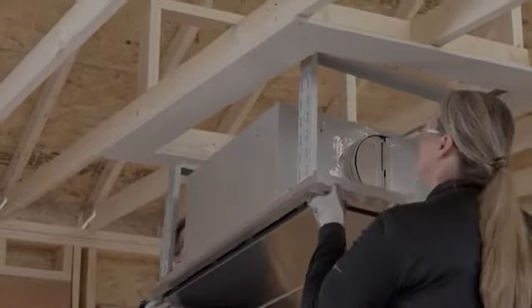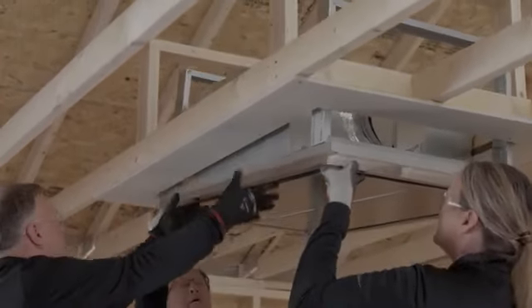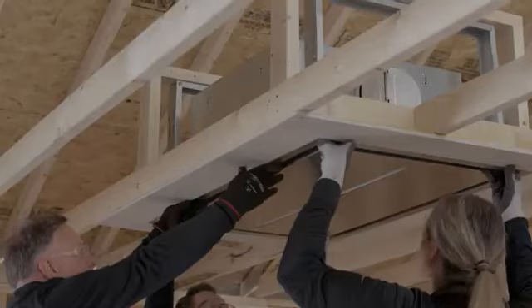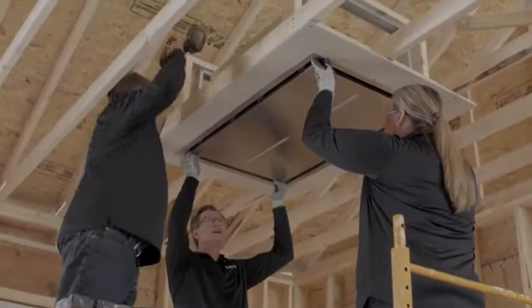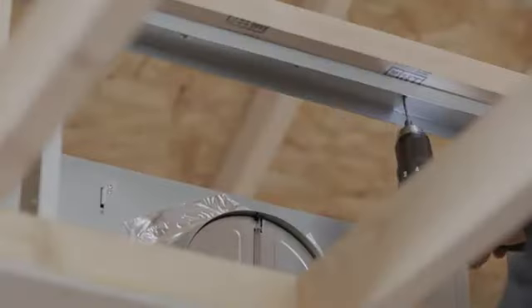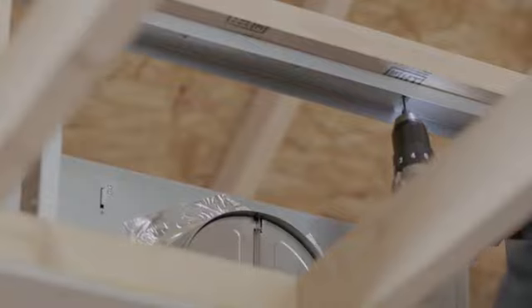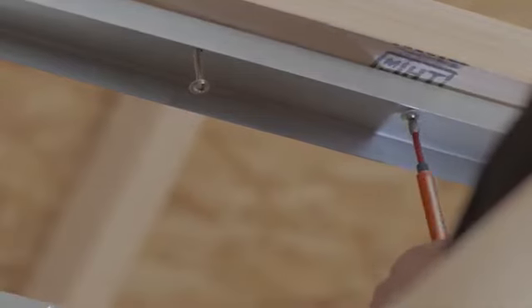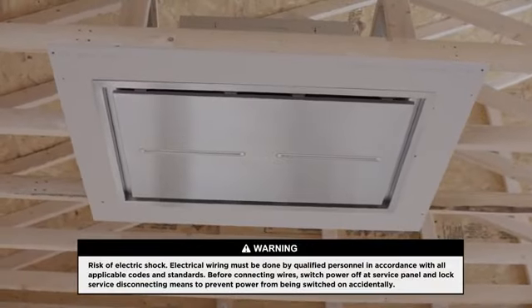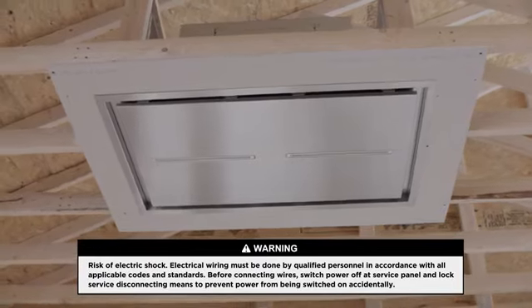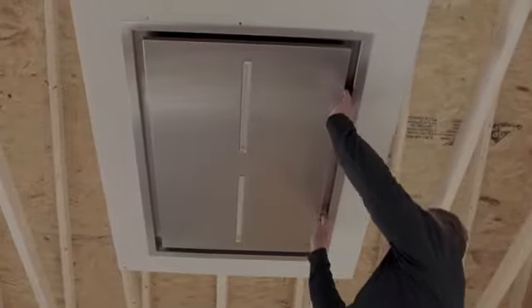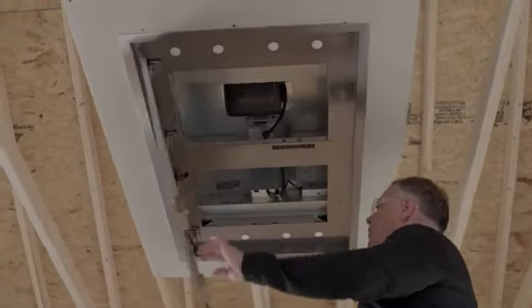When lifting or handling the HBC1, be sure not to lift on the bottom frame of the unit. This reduces risk of damage. Once set, lift the range hood into the ceiling opening. Secure each support frame to the wooden hood support frame using the screws provided. With the hood now secure, you can begin to make all the electrical connections. To prepare the hood for wiring or installation of the blower, push in the 2 lock tabs on the ends of the perimeter panel. Then open the panel and make sure the mesh filters are out.